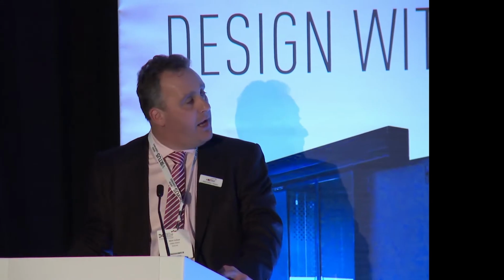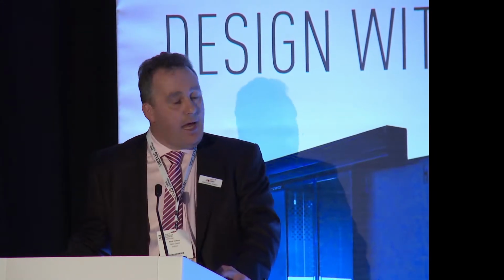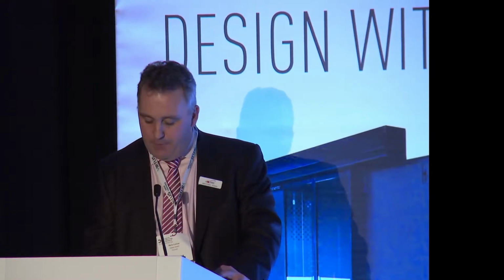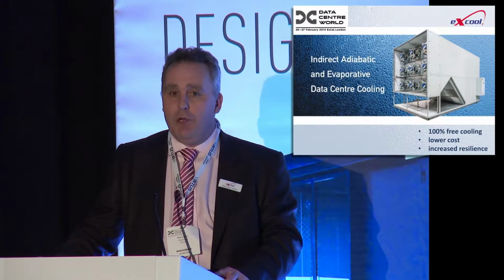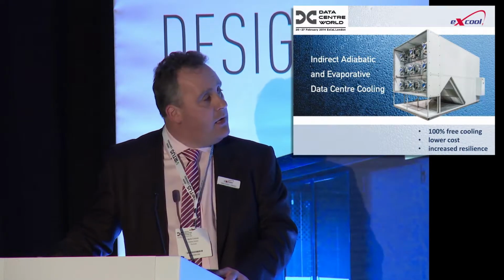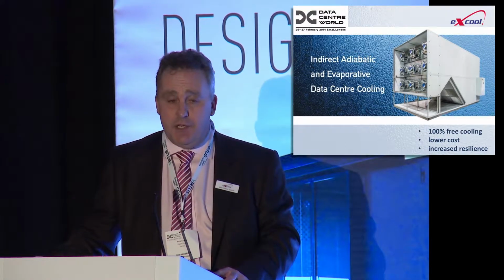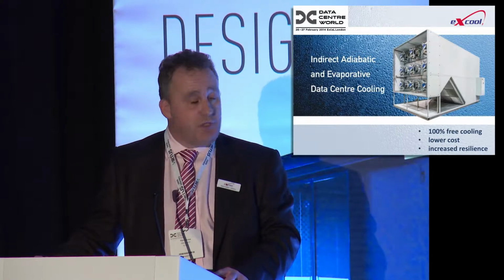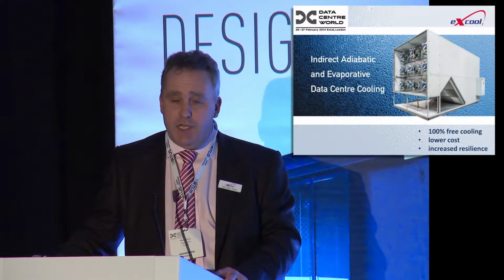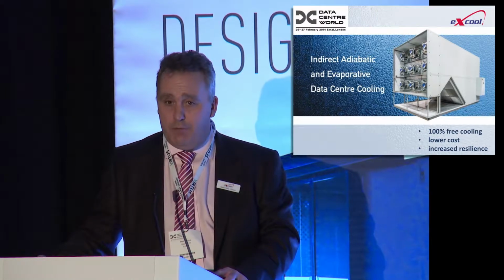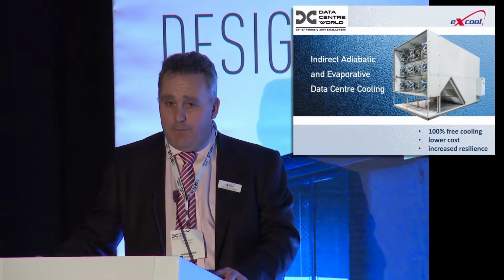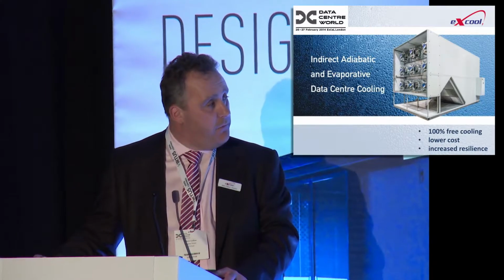I want to talk about a new product that we brought to the market around 2.5 years ago, and is now being distributed around Europe at the moment with plans to take it further afield. The basic concept here is simplicity, and one of the main issues that we want to address is the use of compressor cooling in data centers. We don't feel that there's a real need to use compressors anymore. So we want to see data centers move towards 100% free cooling, which we can achieve throughout most of Europe certainly, and further afield.